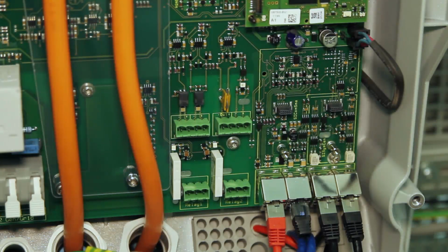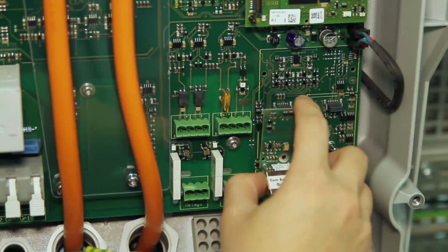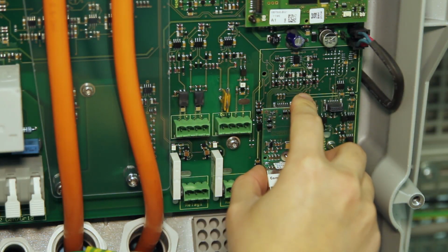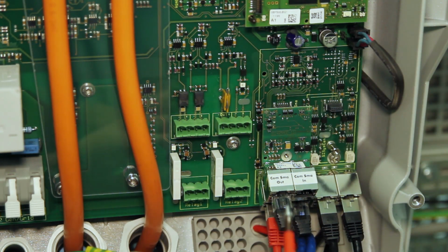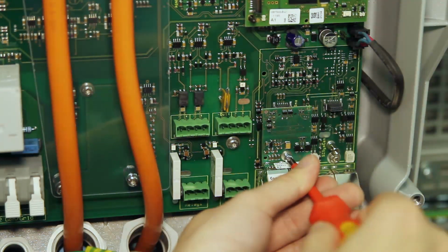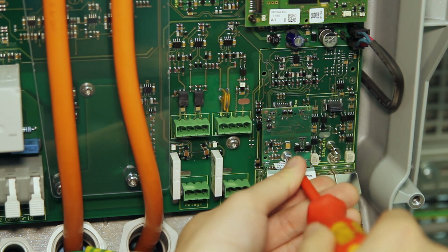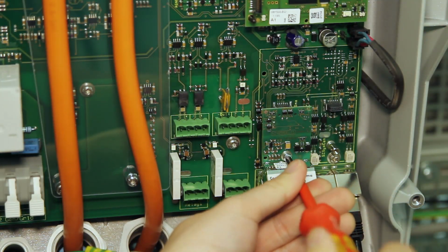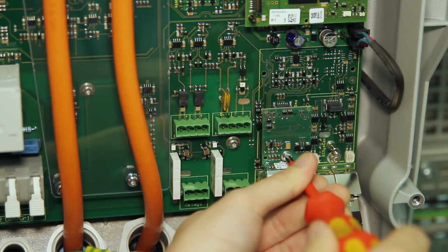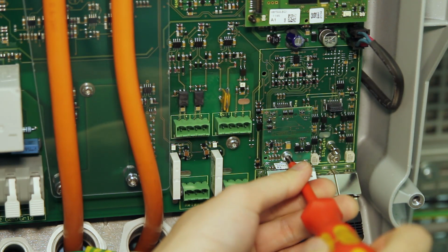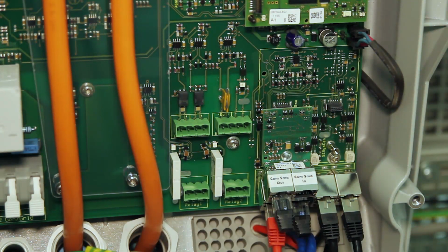To install the card, simply insert it on the mounting hole on the left-hand side interface of your Sunny Island and fasten the screw. For RS-485 devices, a termination resistor is required on the first and last device. If the last device is a Sunny Island, simply insert the resistor on ComSMA in to end the loop.